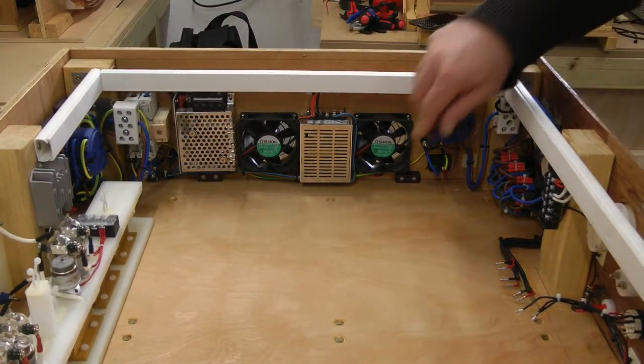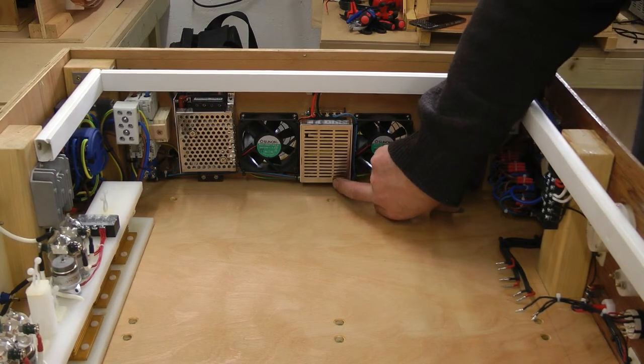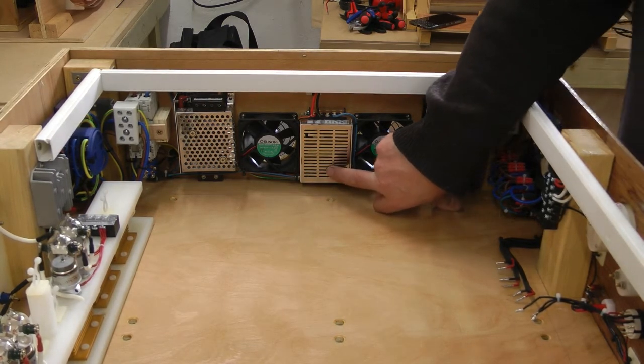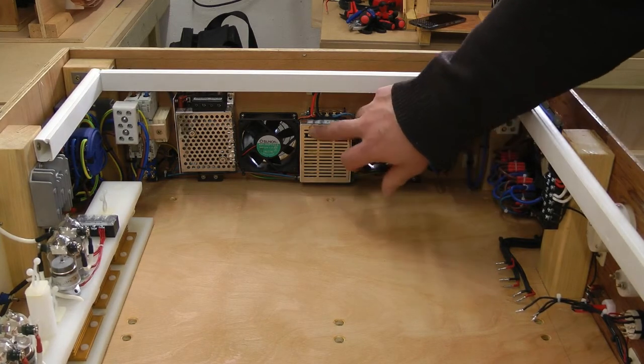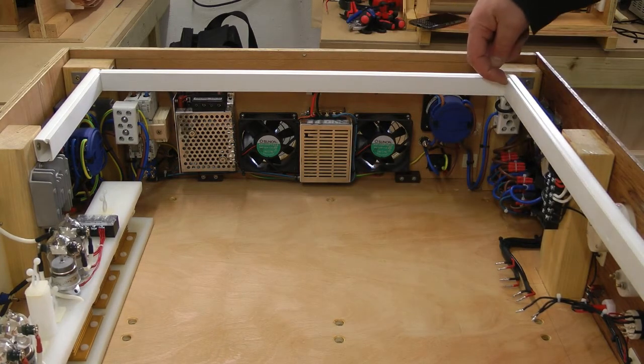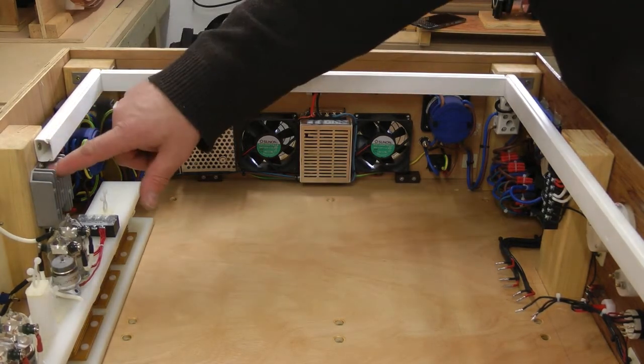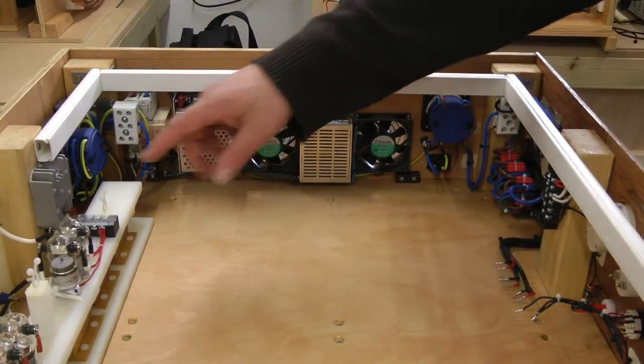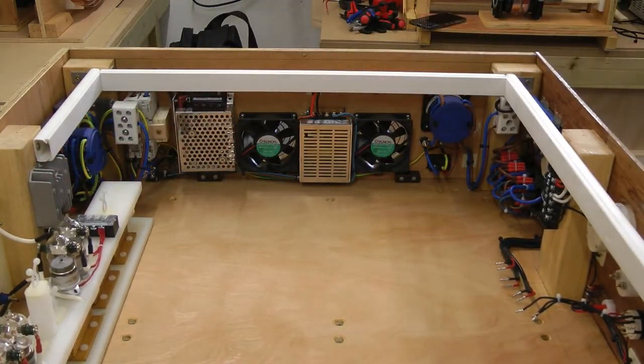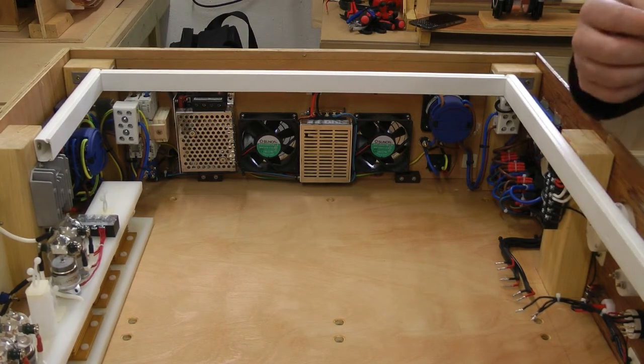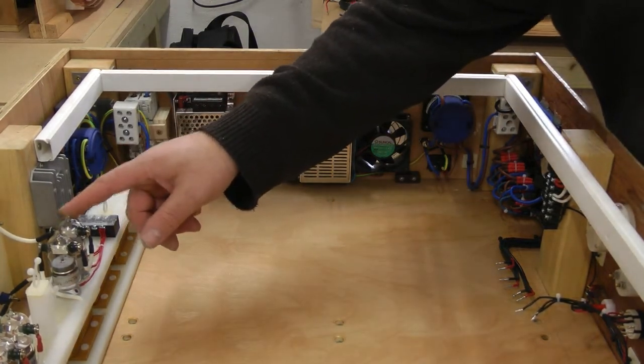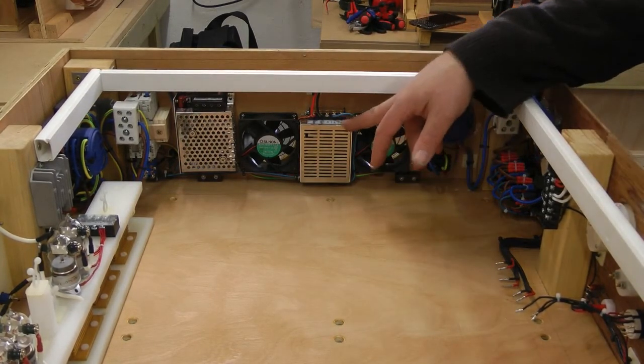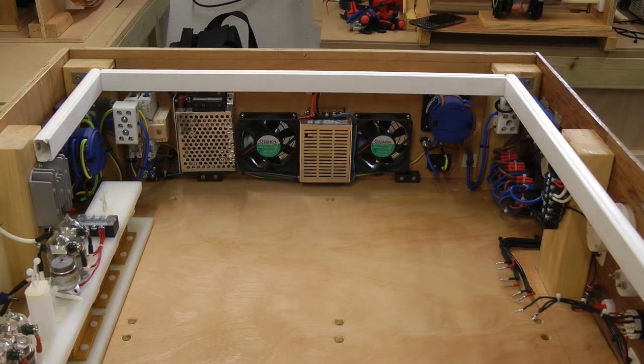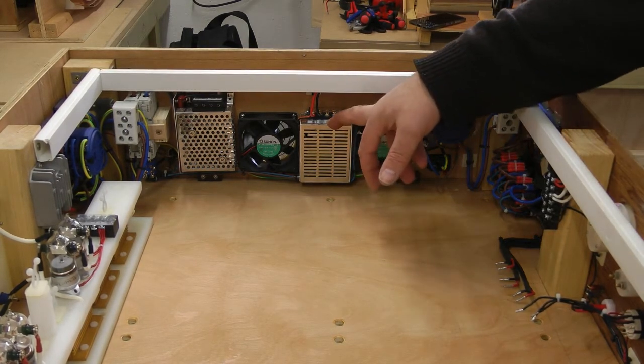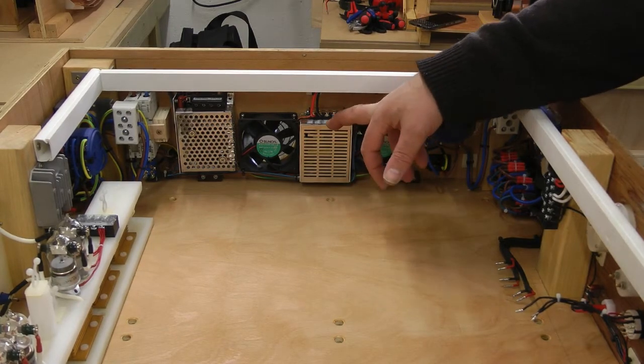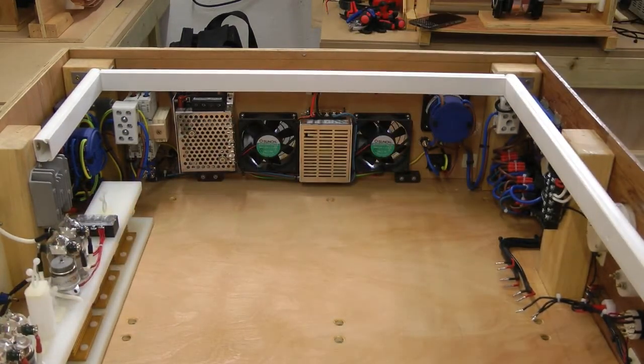So for examples of that, here we've got the 15 volt low tension power supply. It's a 3 amp 15 volt switch mode power supply that feeds power both in this direction to the front panel, and also feeds power down to the 24 volt module. That was the place where I could fit the 24 volt module, and the 24 volt module is primarily used for the switching of the vacuum relays. You can switch those to the 15 volt, but it is not necessarily reliable on all of them. So normally they take up to 27 volts, so 24 volts is a good reliable switching for the vacuum relays.